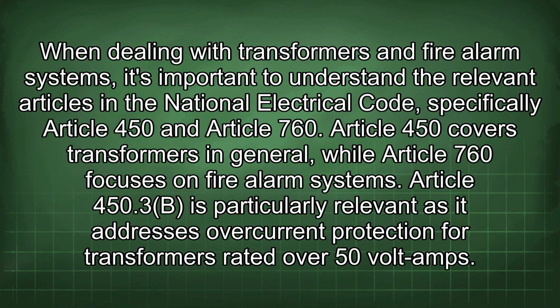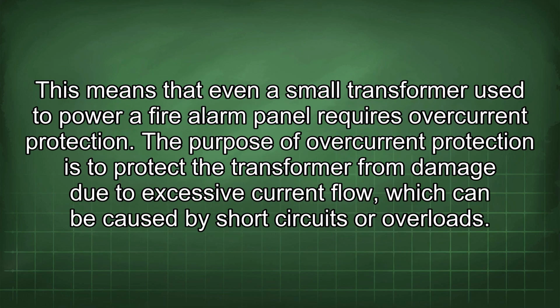When dealing with transformers and fire alarm systems, it's important to understand the relevant articles in the National Electrical Code, specifically Article 450 and Article 760. Article 450 covers transformers in general, while Article 760 focuses on fire alarm systems. Article 450.3(B) is particularly relevant as it addresses overcurrent protection for transformers rated over 50 volt amps. This means that even a small transformer used to power a fire alarm panel requires overcurrent protection.